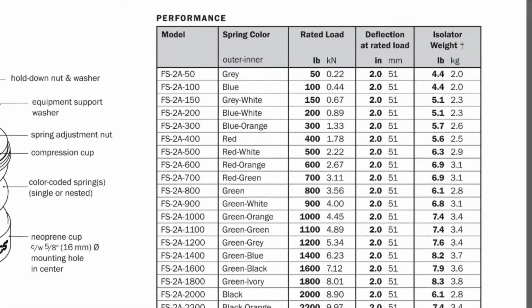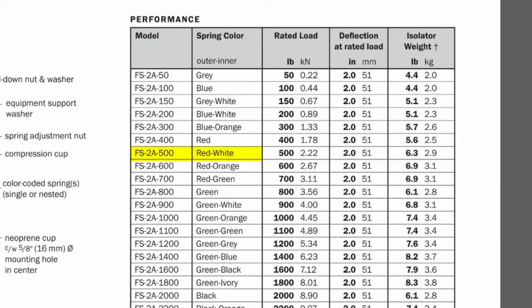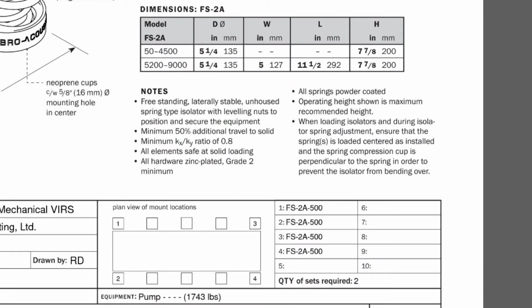As we saw on the inertia base drawing, there will be 4 FS2A 500 isolators supporting the base. As we can see here, the outer spring will be red and the inner spring will be white. We'll look for those spring colors during the walk around. The dimensions for the model used here are shown on this line. The diameter is 5 1/4 inches and the maximum recommended operating height is 7 7/8 inches.